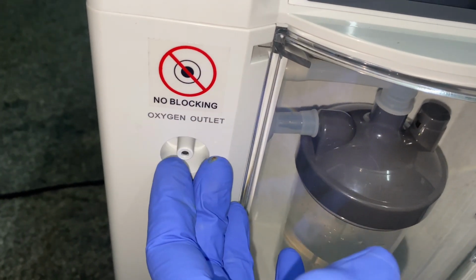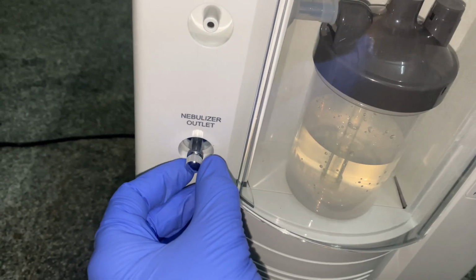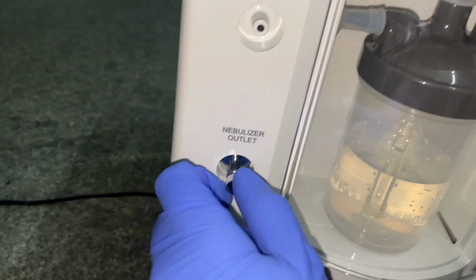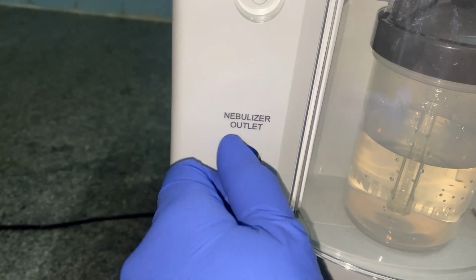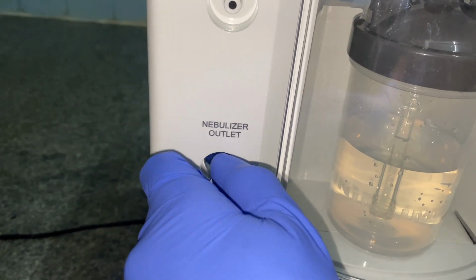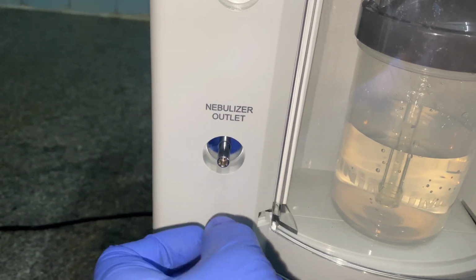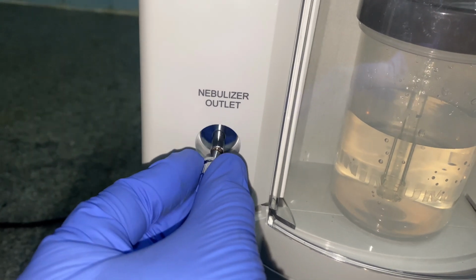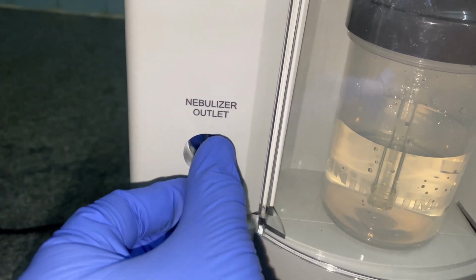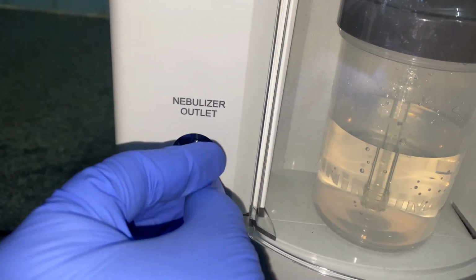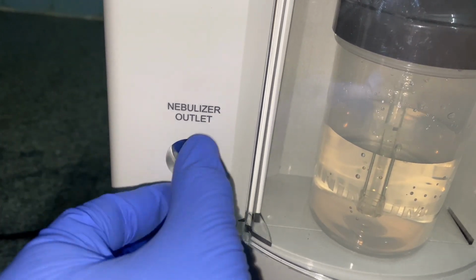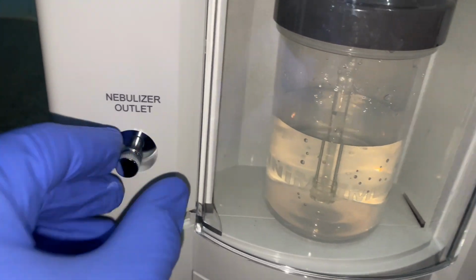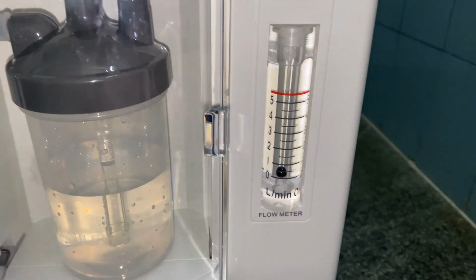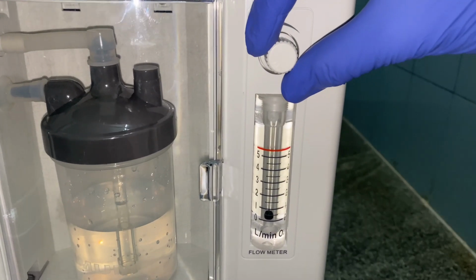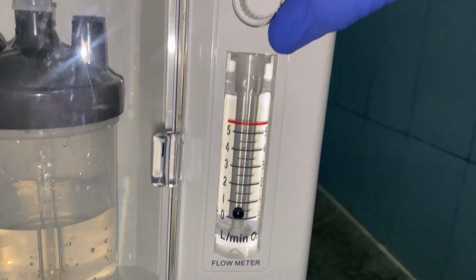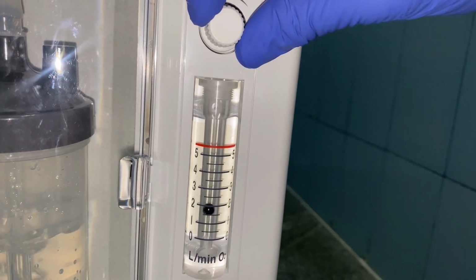Once the instrument is on, we get the oxygen from this knob, which has to be attached with the nasal probe. And if the requirement is there, you can unscrew this and attach this knob for nebulization purpose. If the green light starts blinking, it indicates the system is in good working condition and oxygen concentration is greater than 82%. As the company assures, this gives 93% oxygen.